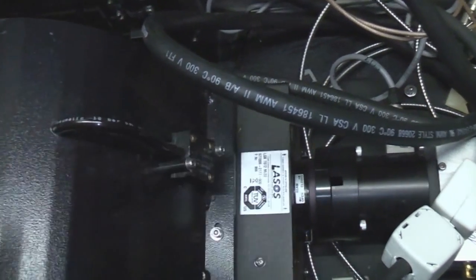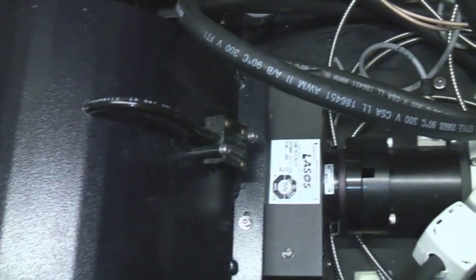There's probably some optical feedback here, because generally you can set these up to give a constant output, adjusting the beam current automatically as the tube ages and the current needed to get a constant output goes up.